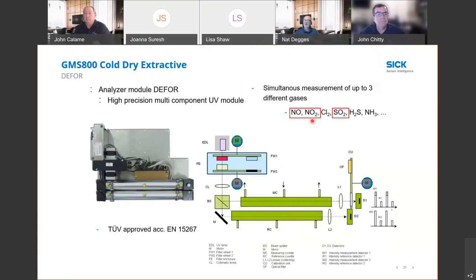So a lot of times NO2 converters will fail the EPA check that you're supposed to do. And you really shouldn't use NO2 bottles. It's a quick and dirty check, but you should really generate the NO2 that you're using to test your converter, because NO2 is highly reactive, and when it stays in the cylinder, it loses its efficacy. So it could be wrong, even though the label says it's certified. After certain periods of time, it reacts with the metal of the cylinder. So generating it is more of a proper way to do it.